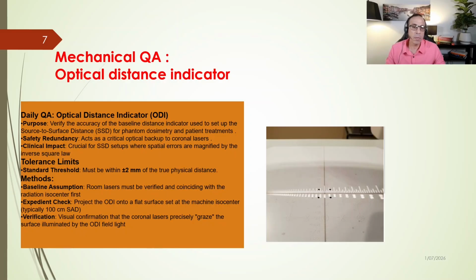To keep our morning workflow efficient, we should use an easy verification method. This procedure assumes that our room lasers have already been checked and correctly coincide with the machine's radiation isocenter. So we place a flat surface on the couch at the exact machine isocenter, which is normally 100 centimeter on the modern linac. We project the ODI onto the surface and verify that our crosshairs match up. The test successfully passes when we visually confirm that the room's coronal lasers precisely graze the exact surface illuminated by the ODI field light.